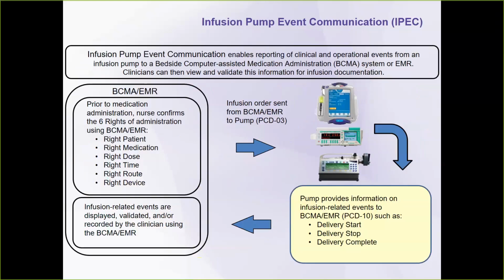Now, after programming, as the infusion is occurring, whether that was programmed manually or in an automated fashion through a PIV, as we just showed, you do need to get the information on pause or resume or other parameters that can be considered as a progress update into the patient's record, or at least into the device's record in some cases. These very commonly go to a bedside medication administration system, BCMA for short, or directly to the EMR for viewing and validation for process. For those transactions, we use the PCD-10 message type in the infusion pump event communication, or IPEC protocol, or profile, I should say.